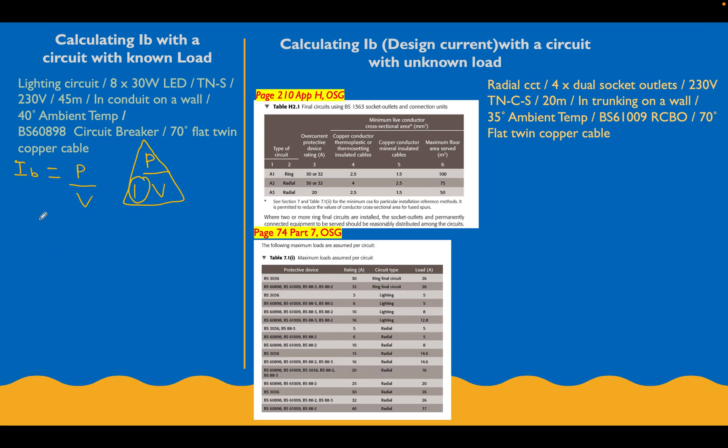For our lighting circuit we've got to work out our power rating: 8 times 30 watt LEDs, so 8 multiplied by 30, which is going to give us 240 watts. That's our power rating for that circuit. So our design current is going to be equal to 240 watts divided by the voltage, 230. When you punch that into your calculator that's going to give you a value of 1.04 amps. That's how easy it is to get the design current for a circuit when we've got a known load. When I say known load, I mean this is a load on the circuit - the 30 watt LEDs.